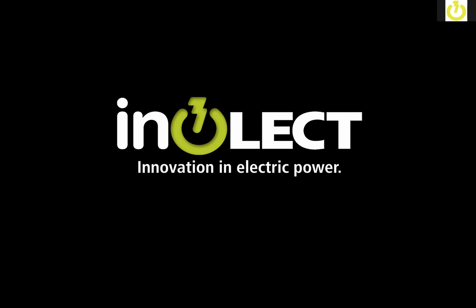Right. Okay, great. That's good to hear. I know some facilities probably have certain vendors that they are required to go with, right? Absolutely. And in some cases, especially with generator protection or GSU step-up transformers, where the generating facility connects to the grid, a lot of times NERC and FERC and those different entities require different manufacturers, and the insurance company also requires different manufacturers, just from a redundant standpoint.